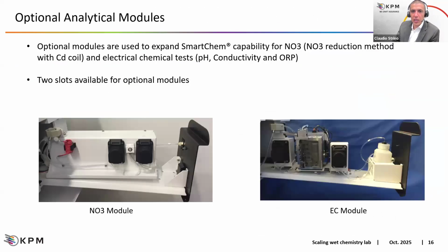This one, perfect. So we have a port where the instrument needle will take sample plus buffer, which could be imidazole if you're running ISO standard methods, or ammonium chloride if you're running EPA methods. Then there is a peristaltic pump that will move the sample plus the buffer into the coil and will flush the sample inside the coil for a specific number of cycles to guarantee the correct reduction yield. Then the reduced sample is moved back to the entry port, and the needle will take only the amount needed to perform the colorimetric testing in the cuvette.